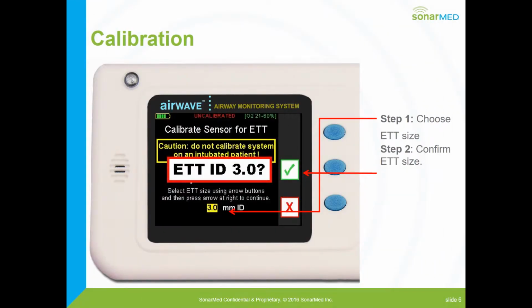So step one is to choose the size of endotracheal tube you're using. At the bottom, you'll see where it says 3.0 millimeter ID. So this would be an example of when I'm using the SonarMed Airwave on a 3.0 endotracheal tube. I choose that size, and if I need to change that, I use my up and down arrows. I press center enter to make that editable, which is a white box, and I use my up or down arrows to choose the appropriate size. Once I've done that, I will get a screen that says, are you sure this is a 3.0? And so I'm going to step 2, confirm it by pushing the button next to the checkbox.